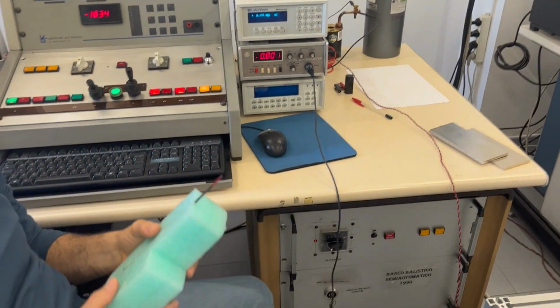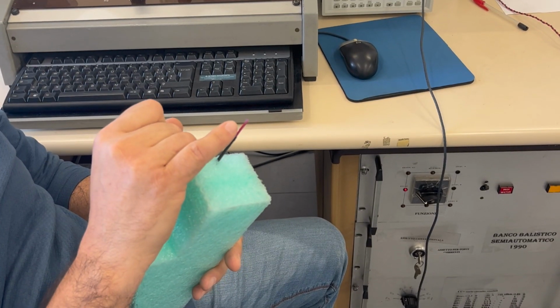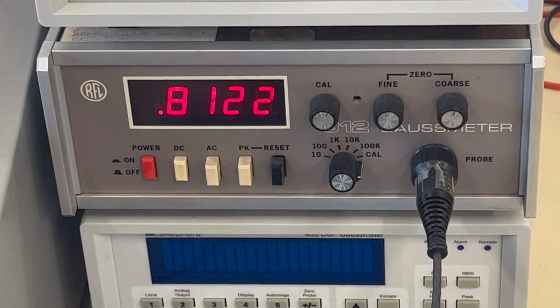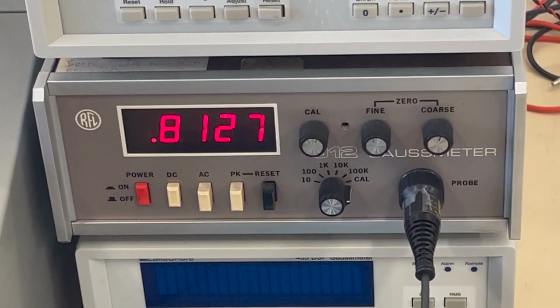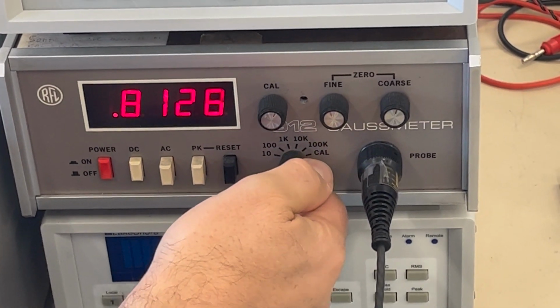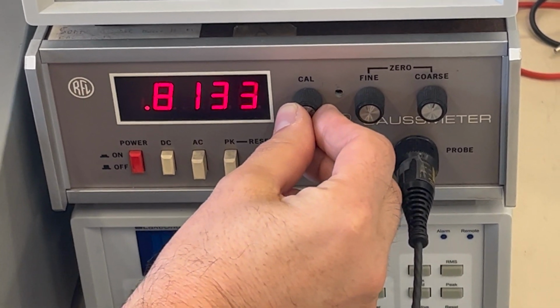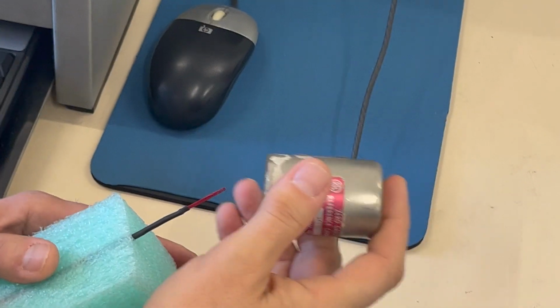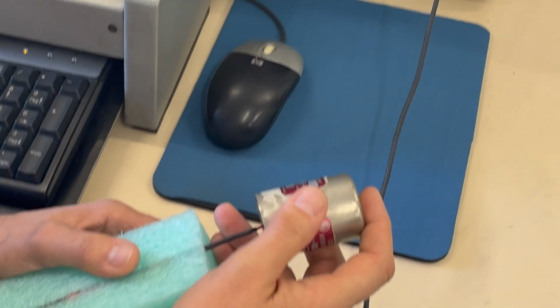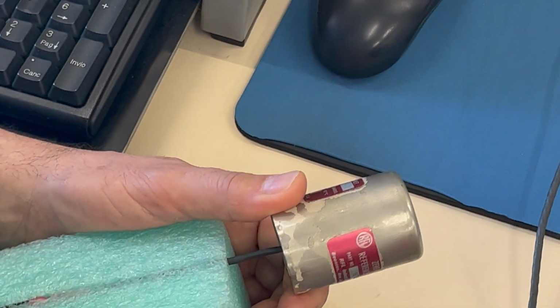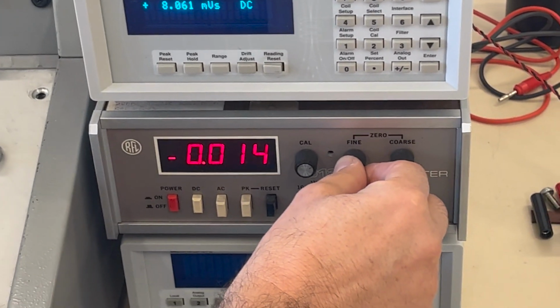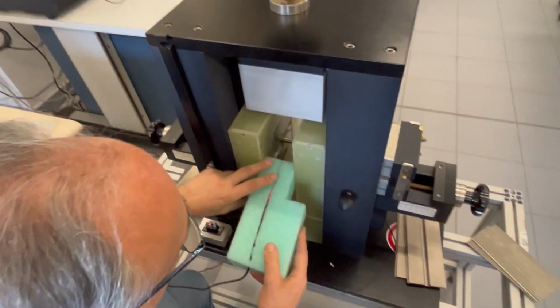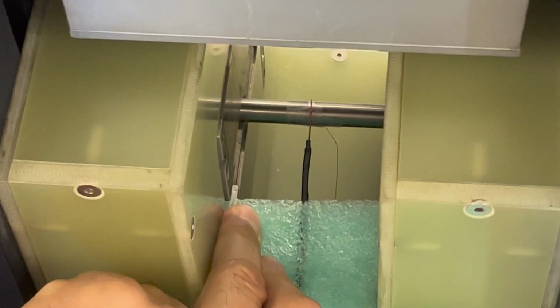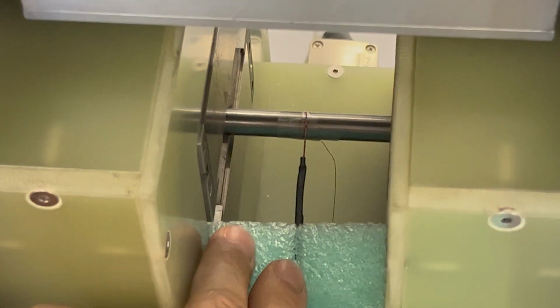To measure the magnetic field to which the sample is submitted, we use a commercial Hall probe, whose sensing element is extremely tiny and is placed at the tip of the probe. Each Hall probe has a different and specific calibration constant. If the gaussmeter does not read it automatically, it must be manually set on the instrument before performing any measurements. Then the probe must be zeroed, preferably with a double-shielded mu-metal null chamber. The probe is placed in close proximity of the sample at the center of the permeameter gap and very, very close to the position where there is the pickup coil.